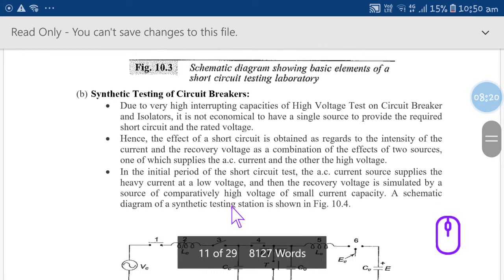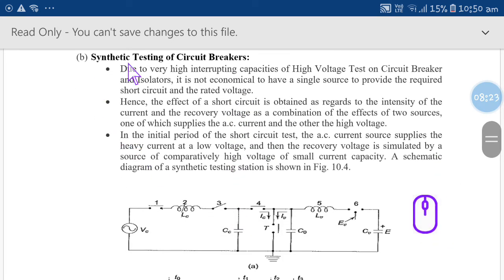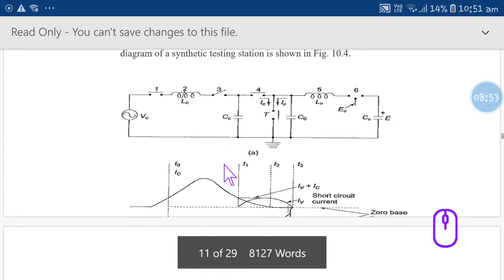B is the synthetic testing. In this synthetic testing, different switches are connected here, okay. Due to the high interrupting capacity required in high voltage testing of circuit breakers and isolators, sometimes it is not economical to use a single source, and different switches have to be used to test the circuit breakers, okay. Therefore an effective short circuit test can be done with the effect of two sources, one which supplies the AC current and the other with high voltage, okay. So now, this schematic diagram is nothing but synthetic testing.